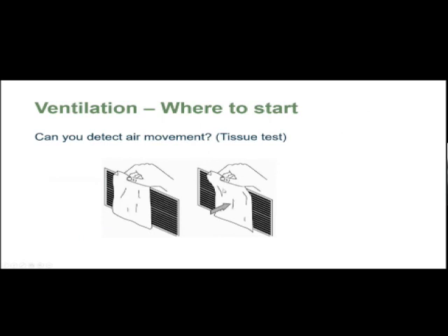Continuing on that theme — these are some of the things we can actually come in and assist you with if you aren't comfortable looking at your own system. When we visit your facility, we'll look at those supply and return vents if you have HVAC. We'll also go into the bathrooms and see if those localized exhausts are actually working, because sometimes they get dirty and stop pulling air outside of the building. One way to tell is to do a tissue test: hold a piece of light tissue up to the vent and it'll pull the tissue back — that's another way to double-check you're getting the dilution necessary to keep the air inside your space clean.